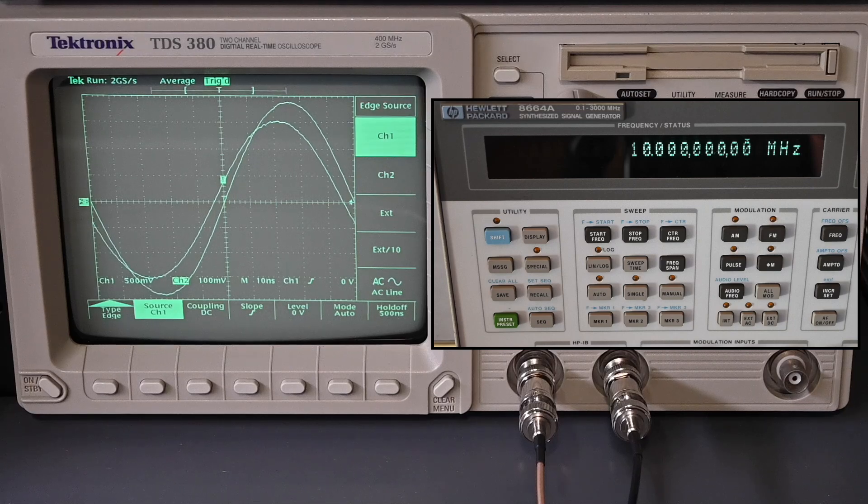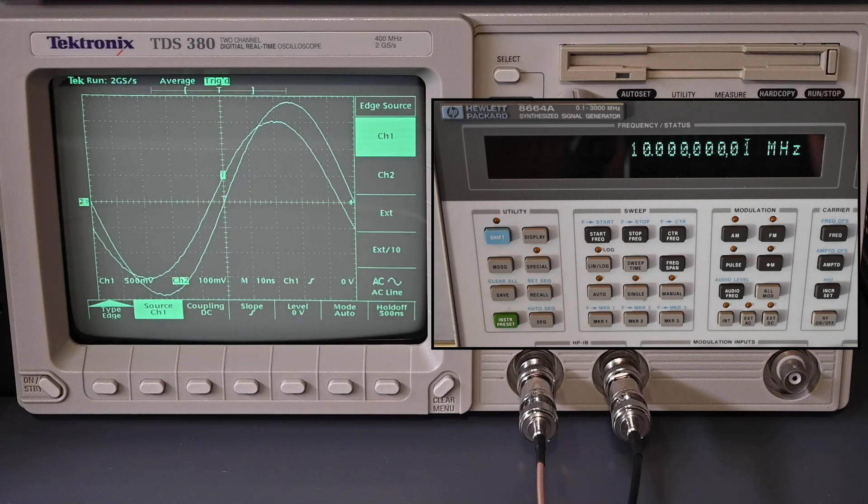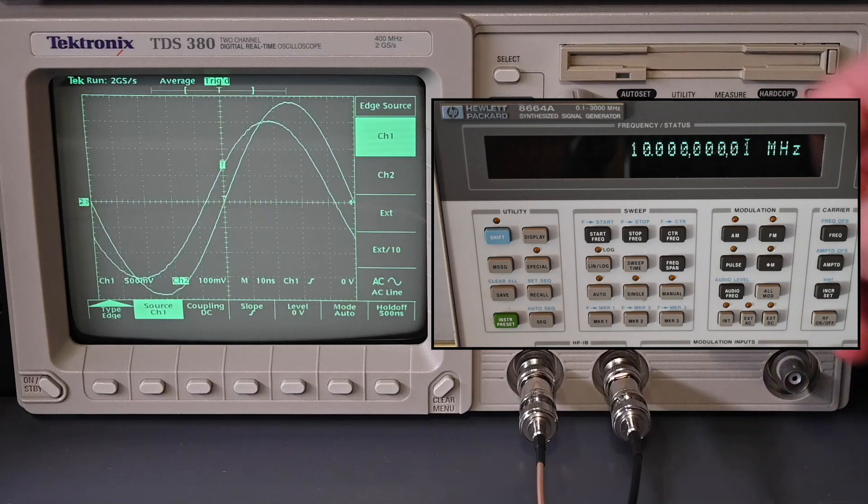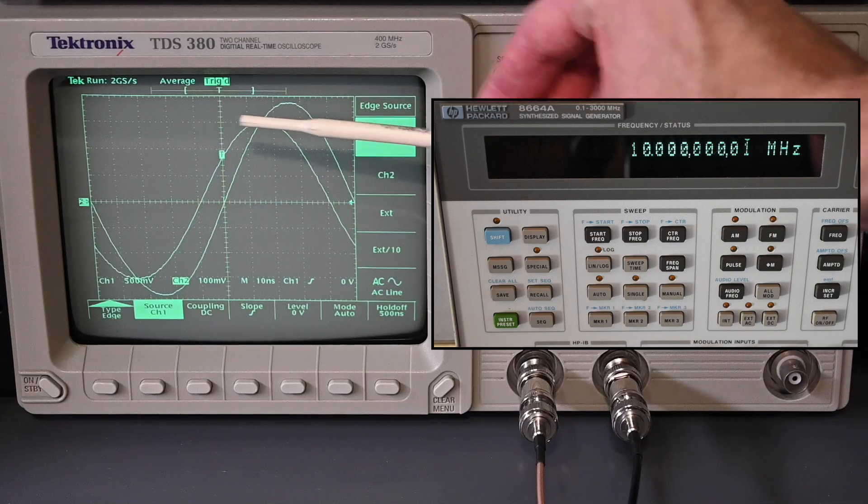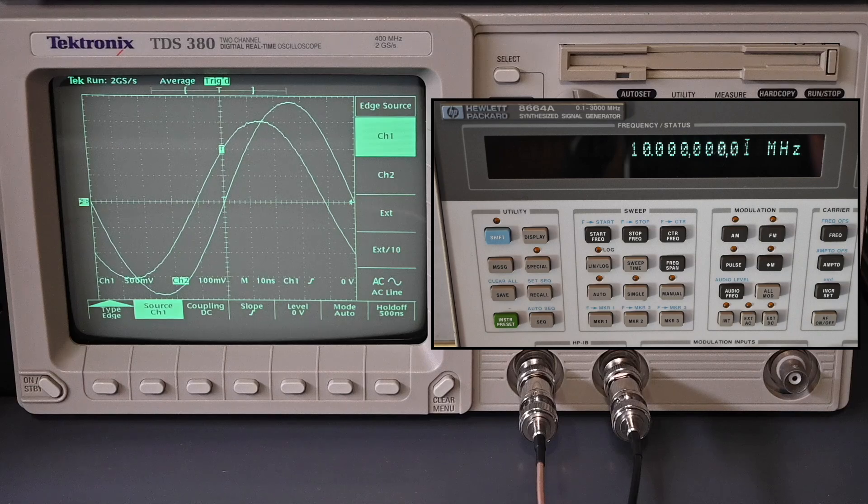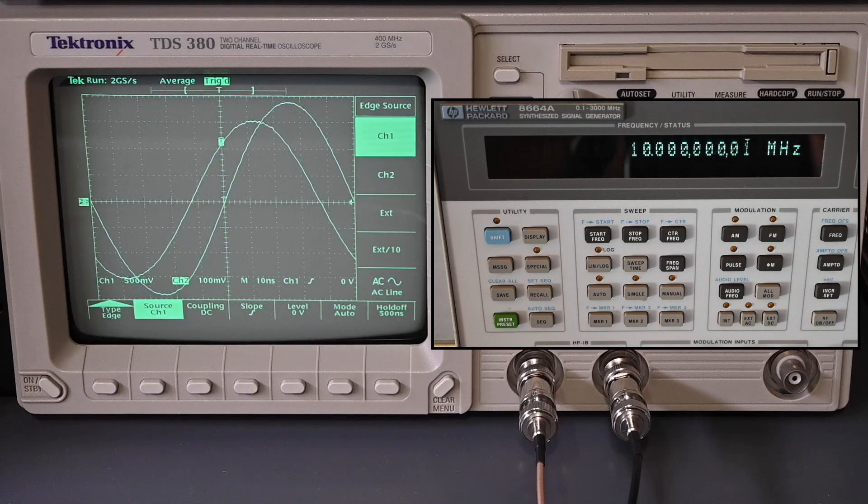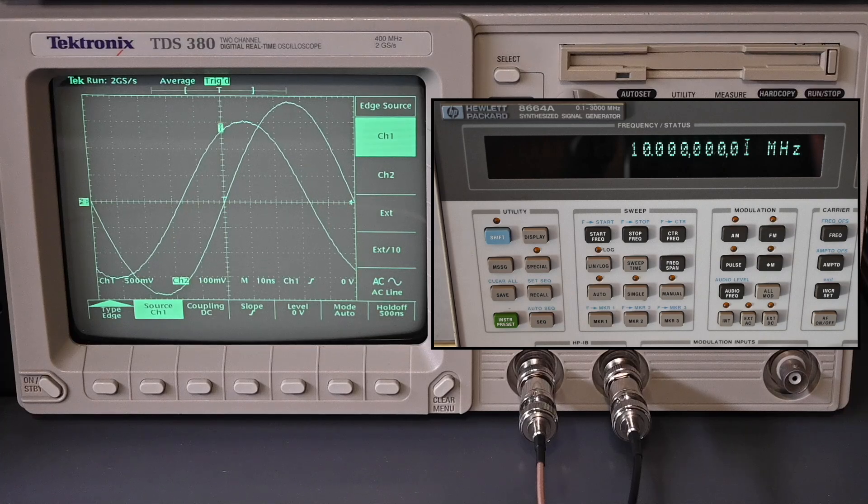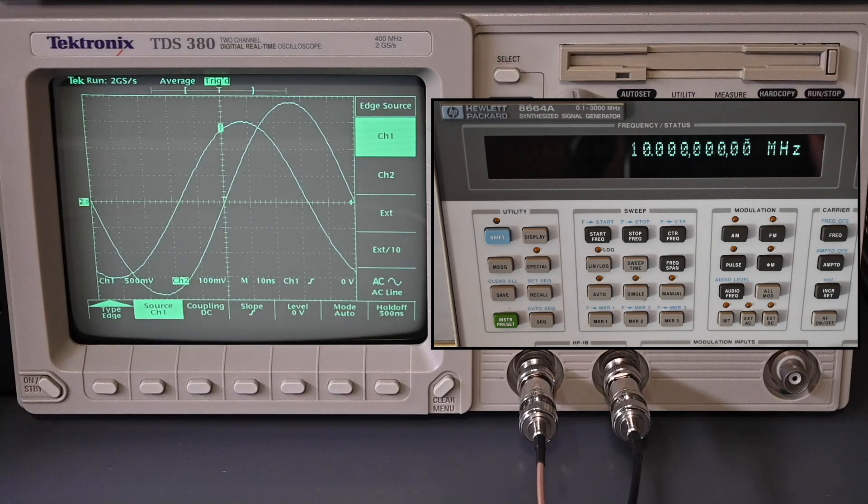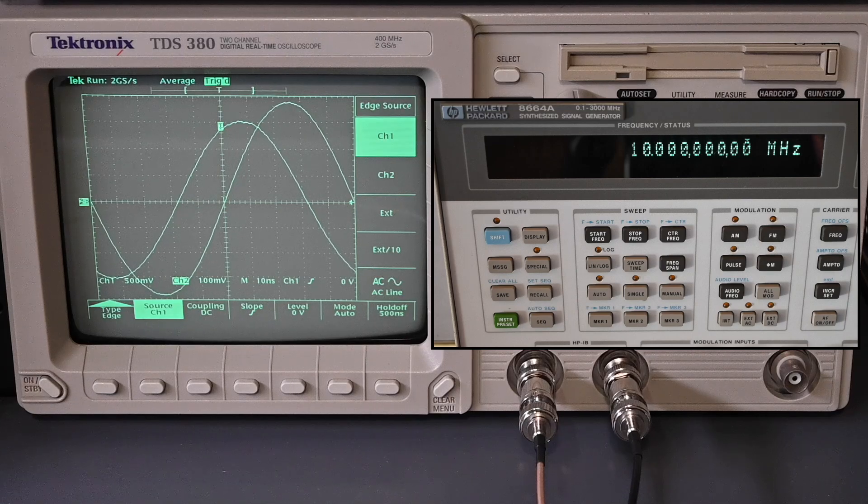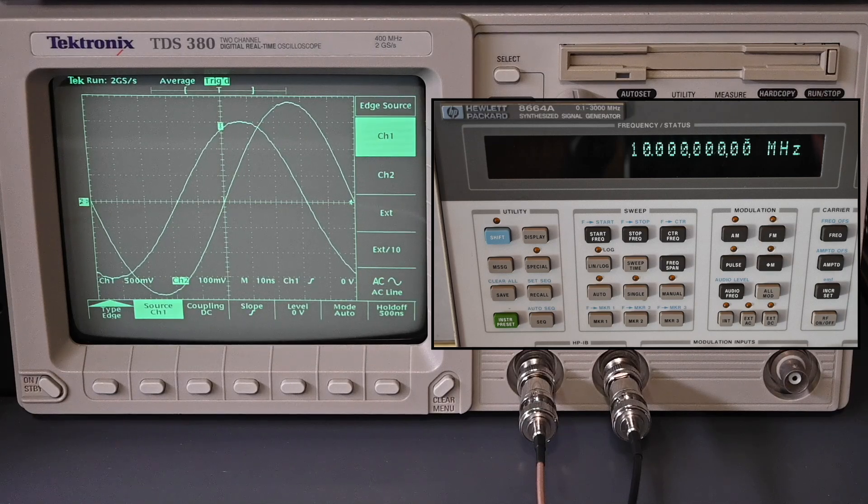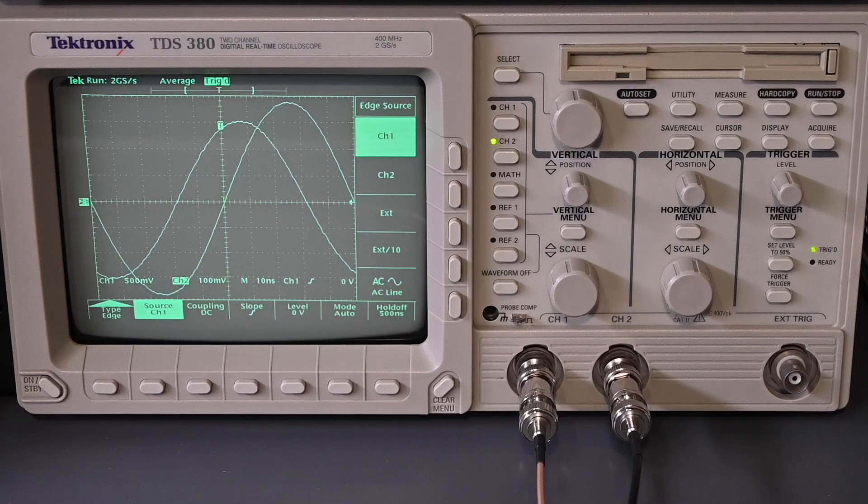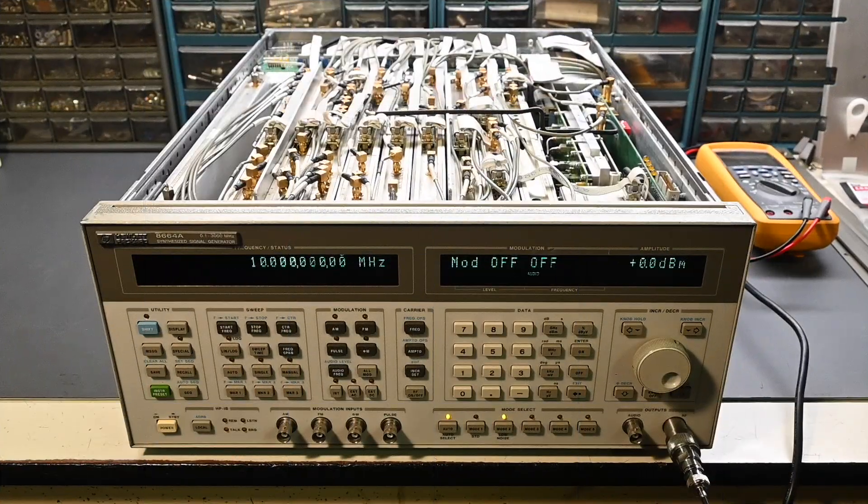I go right exactly back up right there to 10 megahertz, very stable again. And if I go just 10 millihertz above, if you watch, it'll start to drift just a little bit that way. Okay, that's right back to 10 megahertz again, and very stable. So very happy with the result. The signal generator is working very well.